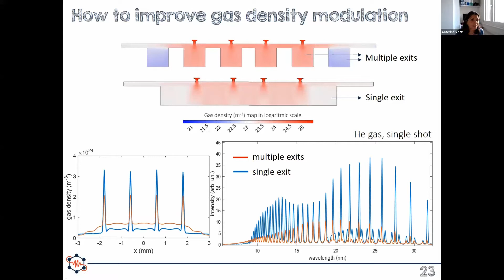But with this new configuration, you get an increase in the modulation of the pressure. And here you can see two harmonic spectra acquired in the same condition for these two devices. The blue one is the one with the single exit, and the red one with the multiple exits. You can see a change in the shape of the spectrum and an increase again of the harmonic emission. So in general, this approach can succeed in getting you a better signal.